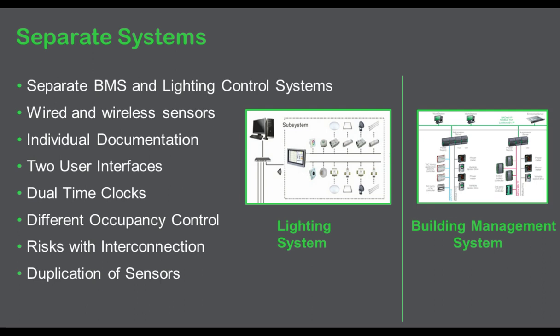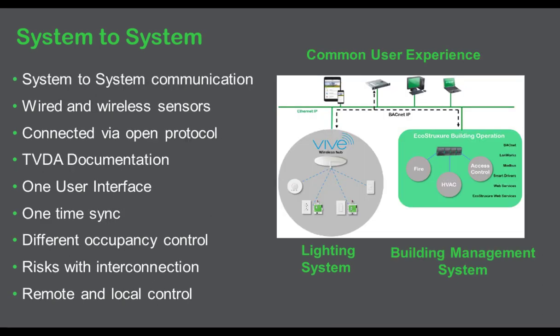Because I typically see where the BMS will have one time clock, time of day, and then the lighting will have another. And I typically have seen where the HVAC will be off, the lighting's on, which doesn't make sense, and vice versa. Well, vice versa causes a bit of a panic because they still want the lights on if it's occupied.